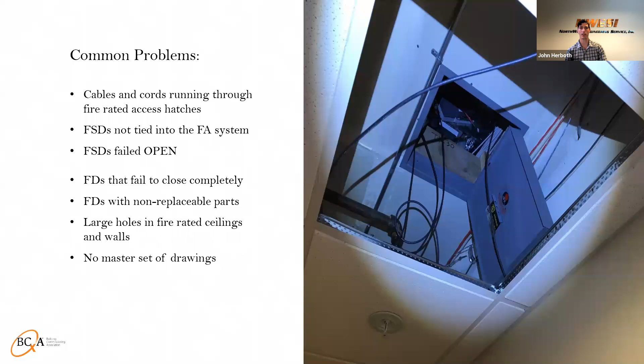We also found some problems with FDs that failed to close completely. That's very common with these flat coil springs I'll show you guys, they just don't have enough tension to pull it closed. And then you'll run into FDs with non-replaceable parts, like this one here, where to test the device you have to destroy it. This little cartridge in the center is what melts and then releases, and there's no easy way to pull it out like a clip.